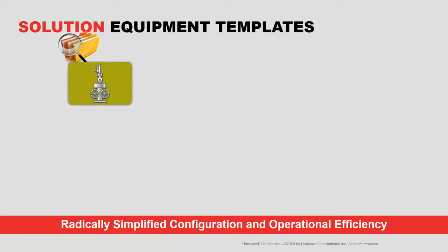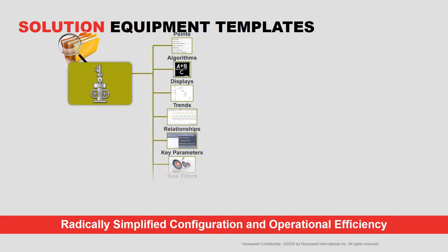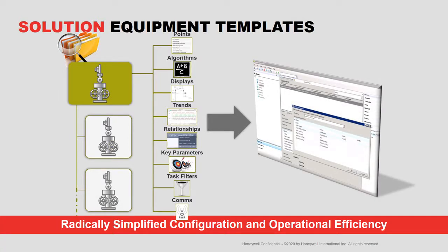One of the key advantages of Experion SCADA is radically simplified configuration and operational efficiency, achieved through a new template-driven concept we call equipment. These templates include all the related SCADA configuration of the equipment: all the points, any calculations, display elements, trend definitions, relationships such as what is upstream or downstream, what are the key parameters for this equipment, the operations task-based filters, even the SCADA communication settings to the RTU or PLC. You then configure a system by adding a single piece of equipment requiring just a few details, instead of separately building many points and operator displays.